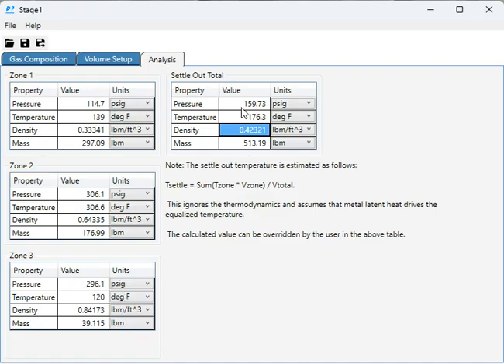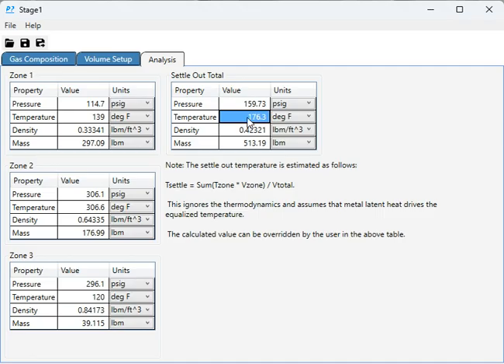And here is the calculated settle-out pressure at this particular assumed settle-out temperature. This is really the trickiest part of the whole analysis, trying to solve what the settle-out uniform or averaged temperature over the entire system is.